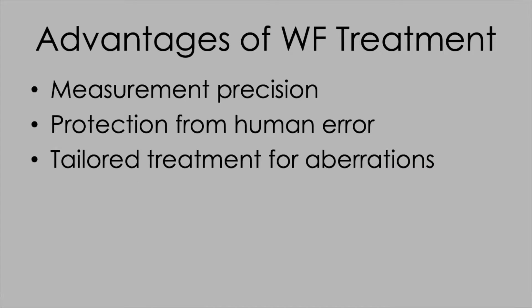What are the advantages of wavefront guided treatment? First of all, measurement precision. Repeatability of measurements is about twice as good as manifest refraction if you're using modern aberrometers, and they protect from human error both in that way and also very importantly by porting the data directly between the scanner, the planning software, and the laser itself — protecting from transcription errors typing in the wrong number or the wrong sign.